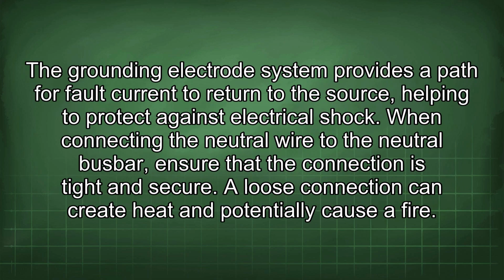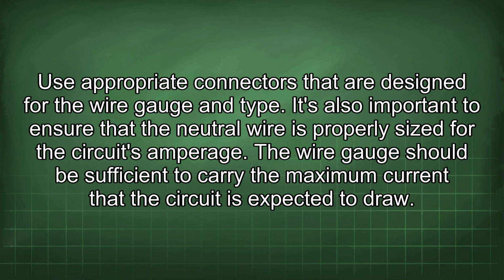The grounding electrode system provides a path for fault current to return to the source, helping to protect against electrical shock. When connecting the neutral wire to the neutral busbar, ensure that the connection is tight and secure. A loose connection can create heat and potentially cause a fire. Use appropriate connectors that are designed for the wire gauge and type.